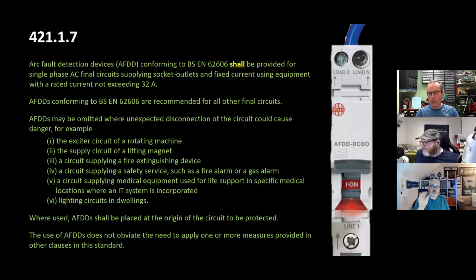Because remember as well, look at that little LED on the front there, that uses energy. So there's a hidden cost of ownership with arc fault detection devices. If you get a 10-way board full of AFDDs and put it on someone in social housing, for instance, it's going to cost energy to run those microprocessors, because in these devices there's a little microprocessor that looks at the sine wave, looks at the waveform, and knows what a good arc is and what a bad arc is.